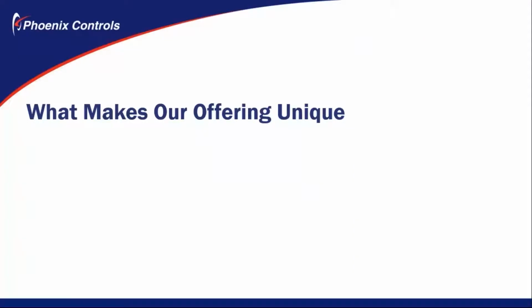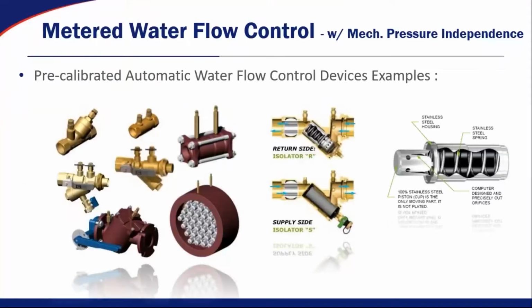So what really makes the Phoenix Controls offering unique? One similar approach to what Phoenix Controls does in regards to airflow can also be applied to water control inside of a building. Most people have heard of a Griswold water control valve when it comes to controlling a fixed volume of water inside of a building. And a Griswold water valve largely works the same principles as a Phoenix Controls valve uses. So inside of a Griswold water valve, you have a calibrated spring that needs a minimum differential pressure required to compress that spring and get that valve into its control range. And then anything above that minimum pressure will give you a constant volume of water going through that valve.